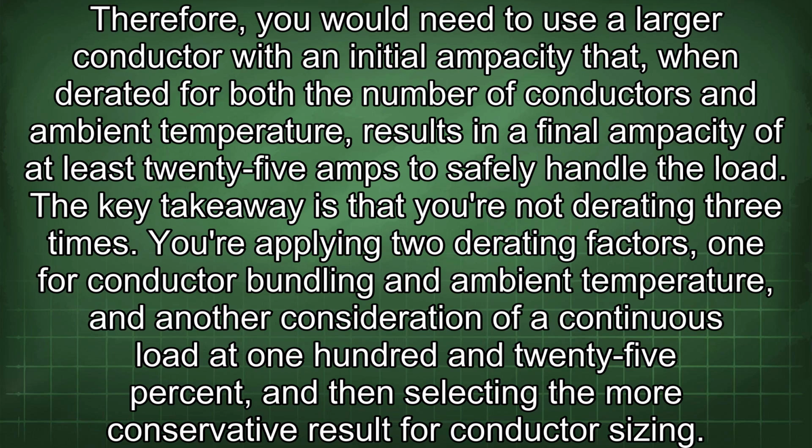The key takeaway is that you're not derating 3 times. You're applying 2 derating factors, one for conductor bundling and ambient temperature, and another consideration of a continuous load at 125%, and then selecting the more conservative result for conductor sizing.